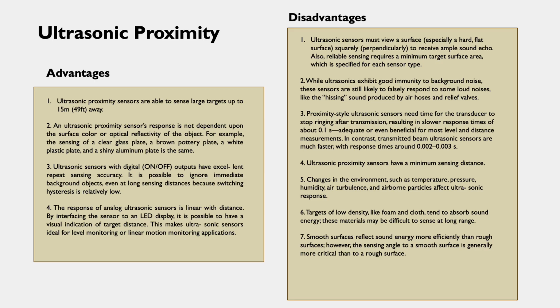Number 3, ultrasonic sensors with digital on and off outputs have excellent repeat sensing accuracy. It is possible to ignore immediate background objects even at long distance because switching hysteresis is relatively low.